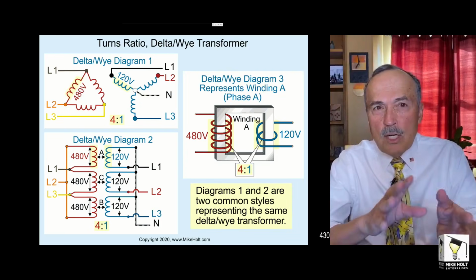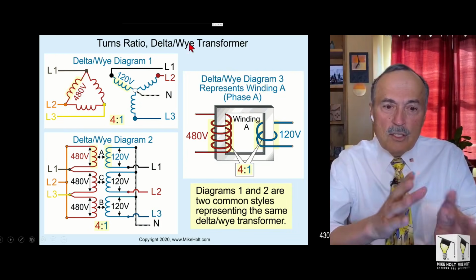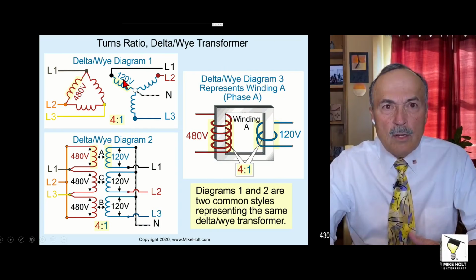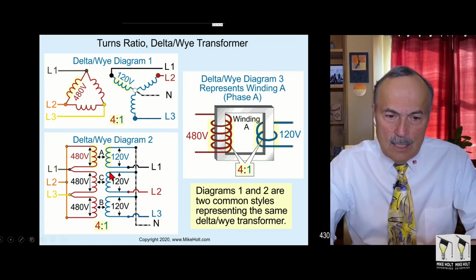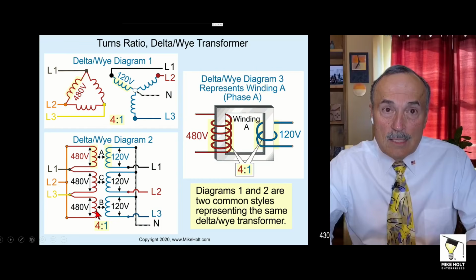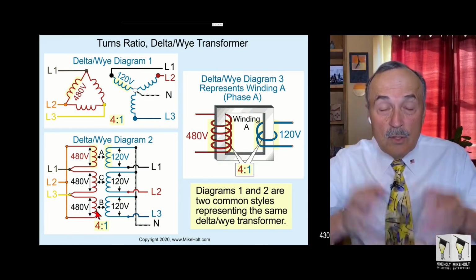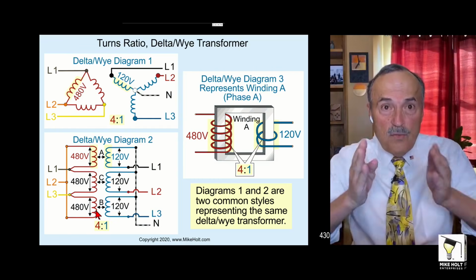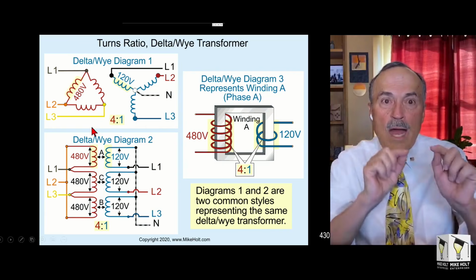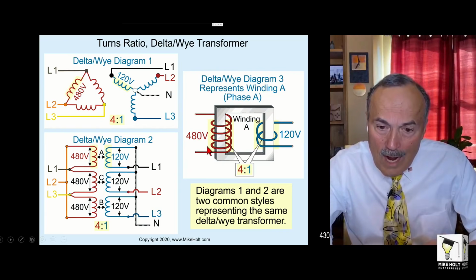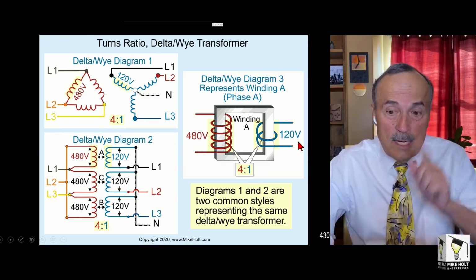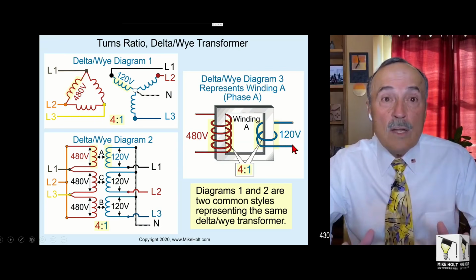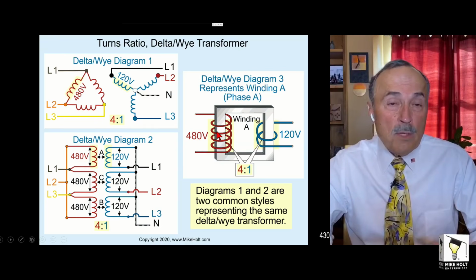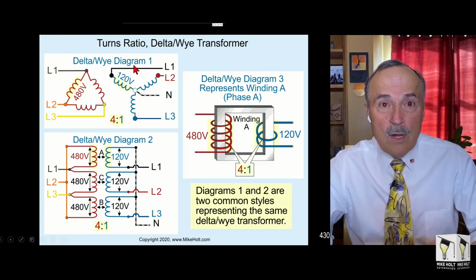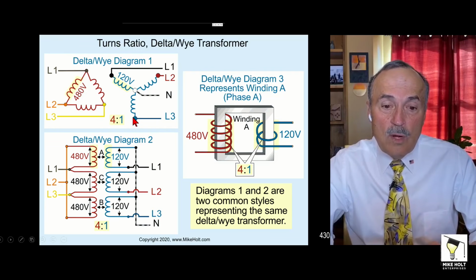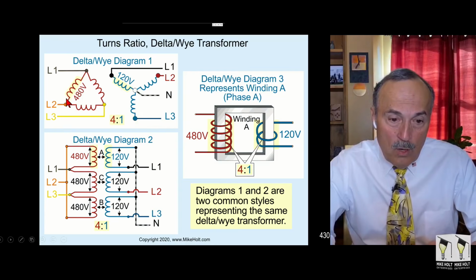I'm adding a new graphic, a little different than what we've been doing, to try to show you. Remember we talked about that delta-Y configuration? Well, in reality, it is 3 separate phases. That's why it's called a 3-phase system. So there are 3 separate transformers, and it's just a matter of how they're wired. Look, there's only 2 wires on the primary of this one phase, and only 2 wires on the secondary of the one phase. Well, if the primary is 480 coming in, and you wanted to get a 120/208Y secondary, well, it's a delta.